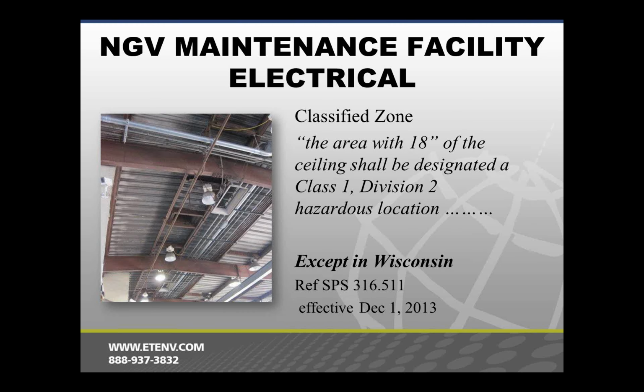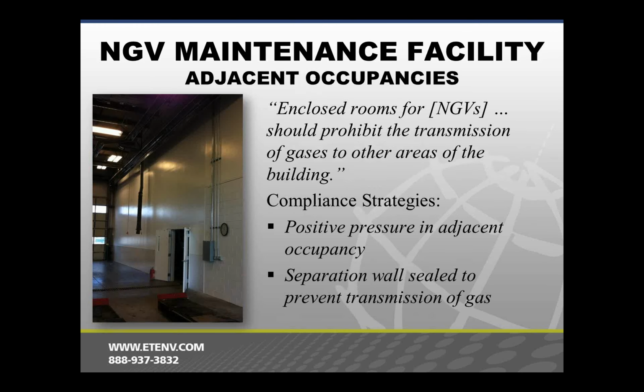The next subject is adjacent occupancies, and what we need to do is basically keep the hazardous environment, or natural gas, up near the ceiling from migrating to adjacent spaces such as offices or wash bays if those are not going to be set up to be compliant. There are several ways to accomplish that, either with positive pressure in the adjacent occupancies or just sealed separation walls.